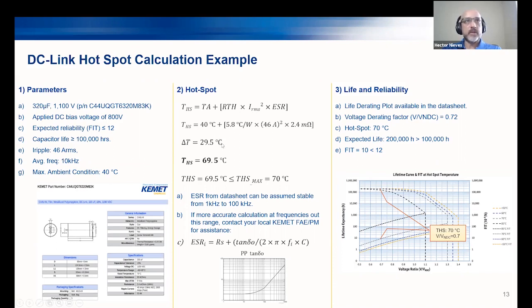So it's a simple calculation: 29.5, almost 30 Celsius degree hot spot rise. You add that to the 40 Celsius degrees, and you have a hot spot temperature of almost 70 Celsius degrees, which is within the range of this capacitor. So in this case, you can see it's acceptable.